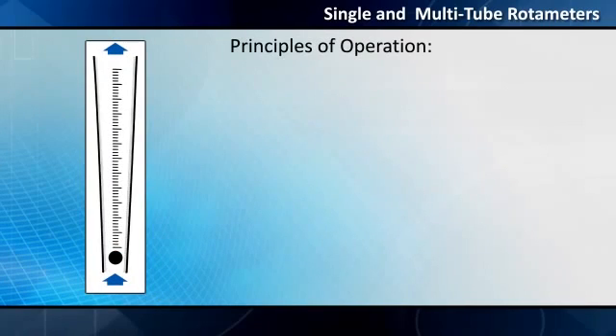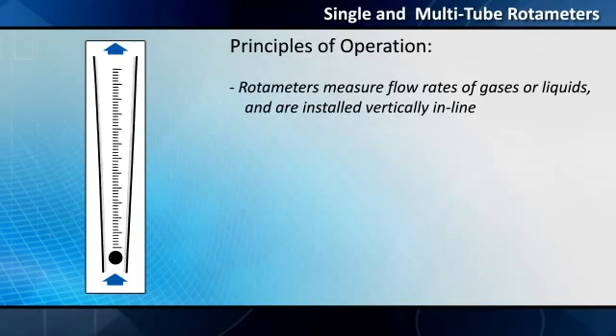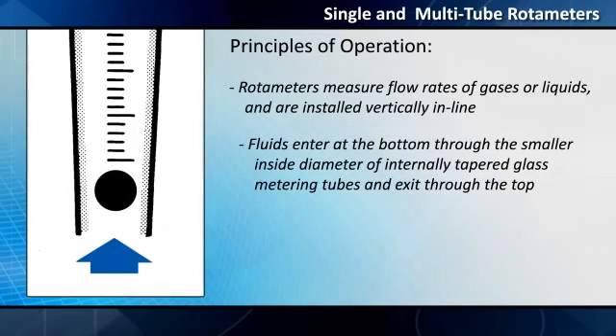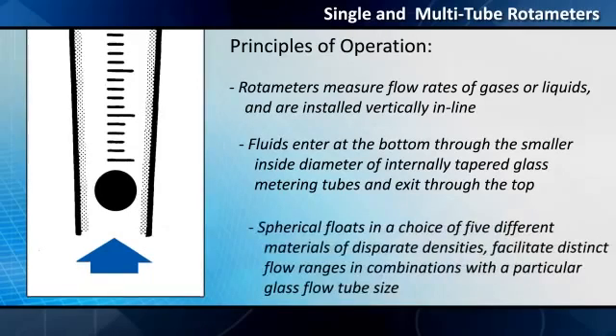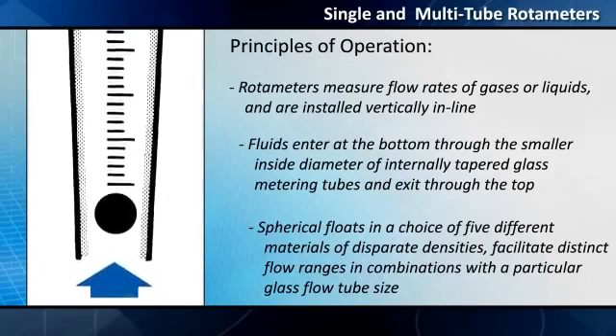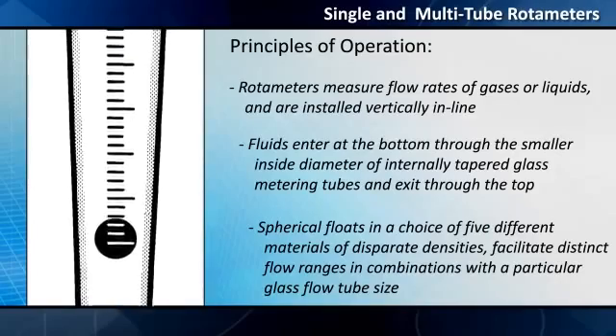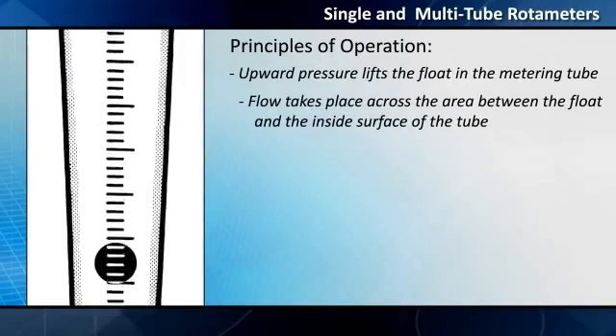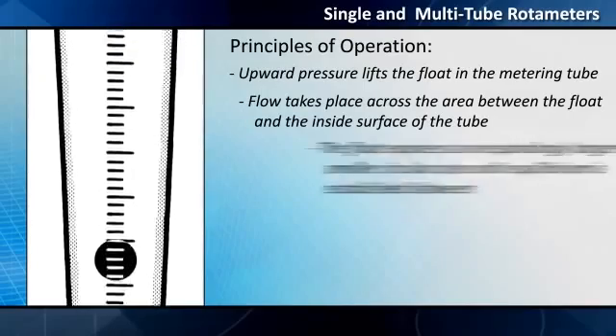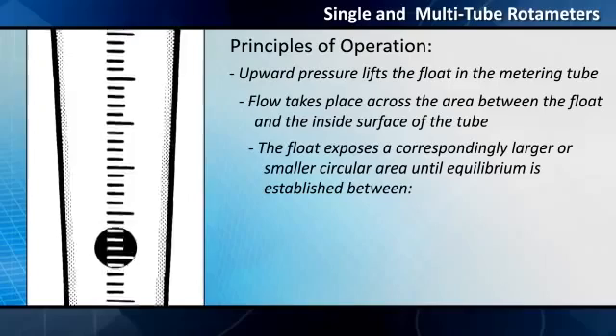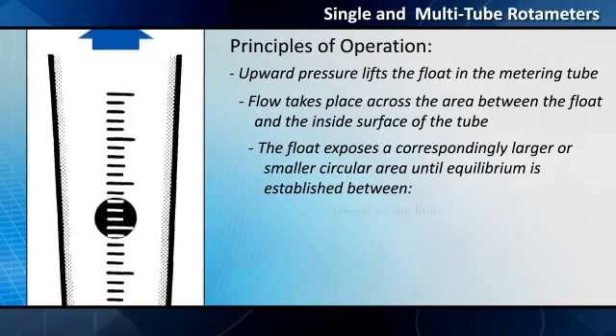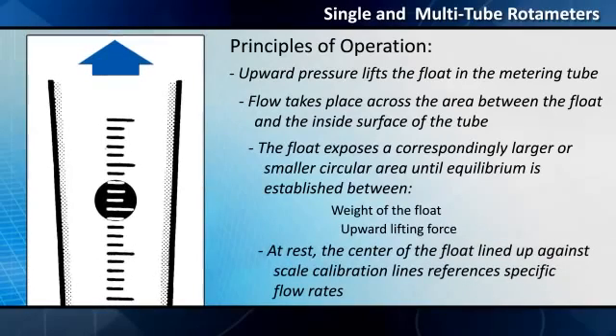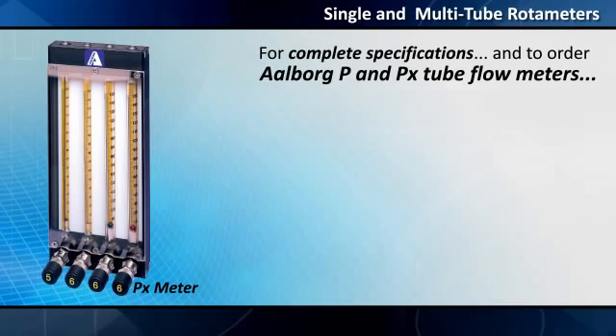Principles of operation: Rotometers measure flow rates of gases or liquids and are installed vertically in line. Fluids enter at the bottom through the smaller inside diameter of internally tapered glass metering tubes and exit through the top. Spherical floats in a choice of five different materials of disparate densities facilitate distinct flow ranges and combinations with a particular glass flow tube size. Upward pressure lifts the float in the metering tube. Flow takes place across the area between the float and the inside surface of the tube. As flow rates change, the float exposes a correspondingly larger or smaller circular area until equilibrium is established between the weight of the float and the upward lifting force on it. At rest, the center of the float lined up against scale calibration lines references specific flow rates.